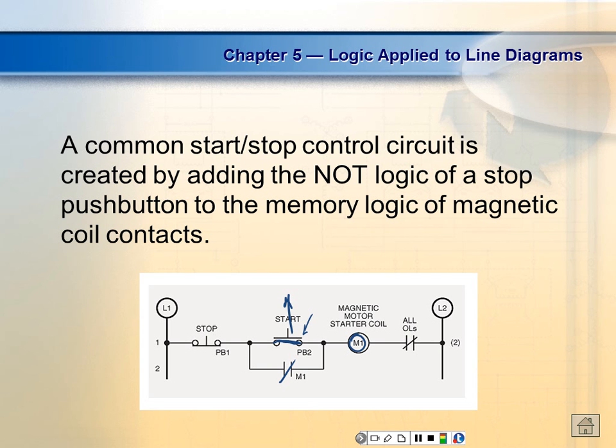And then what would be required to get it going again? Just push start? Well, yes and no. We have to go over here and reset the overload. It depends on what type of motor it is. Most of your industrial motors, though, have to be reset. You know, for obvious reasons, because those big old motors can cause damage.